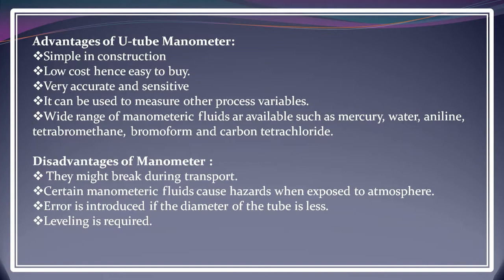Disadvantages of the manometer include: they might break during transport because they are made of glass or transparent metal. Certain manometric fluids such as mercury, tetrabromomethane, and other corrosive liquids are hazardous to the environment and to us. Error is introduced if the diameter of the tube is too small. Leveling is also required — before attaching any U-tube manometer to a process, the manometric fluid must be at zero, otherwise the reading will be faulty.